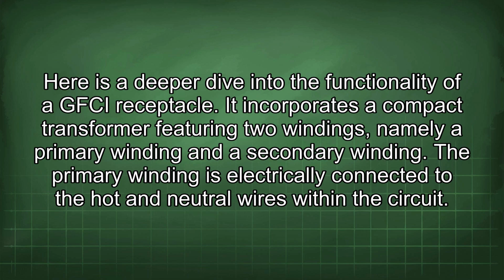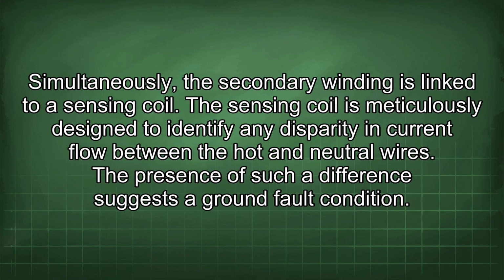It incorporates a compact transformer featuring two windings, namely a primary winding and a secondary winding. The primary winding is electrically connected to the hot and neutral wires within the circuit. Simultaneously, the secondary winding is linked to a sensing coil. The sensing coil is meticulously designed to identify any disparity in current flow between the hot and neutral wires. The presence of such a difference suggests a ground fault condition.